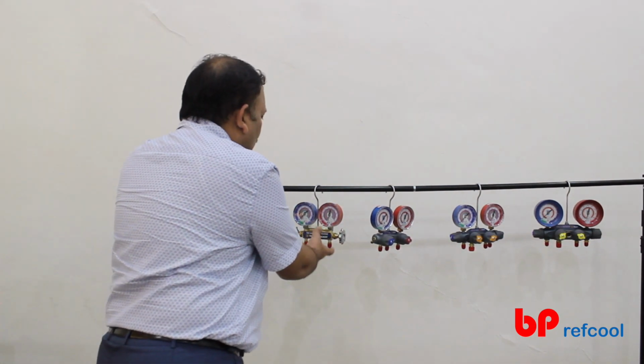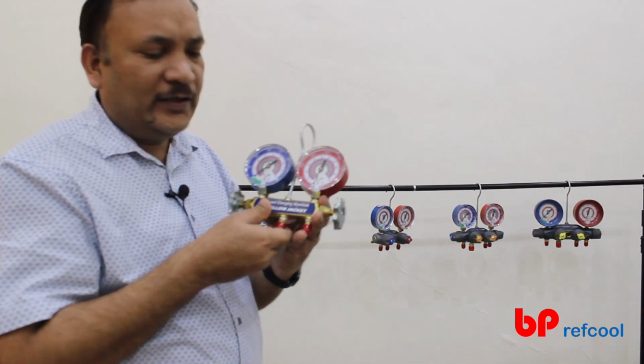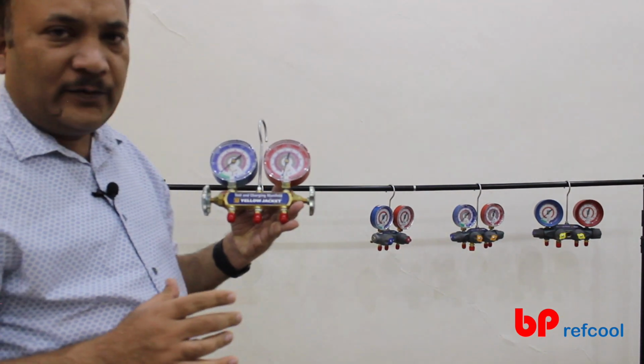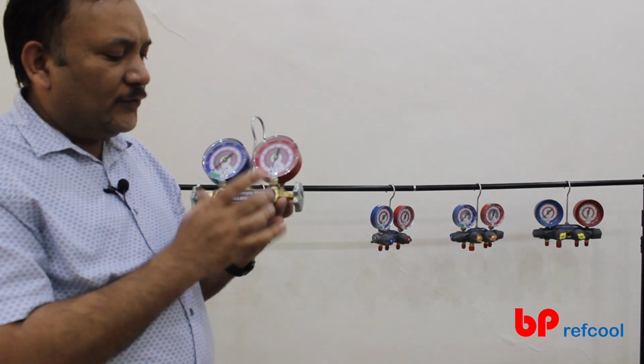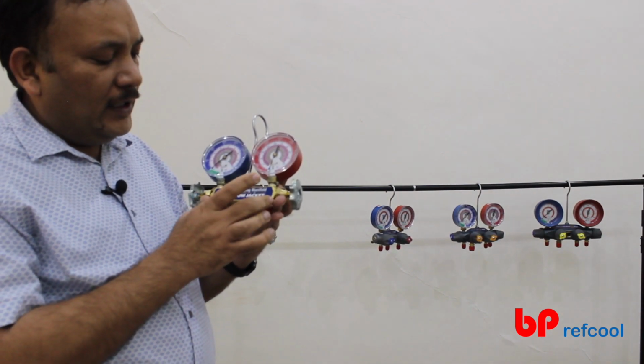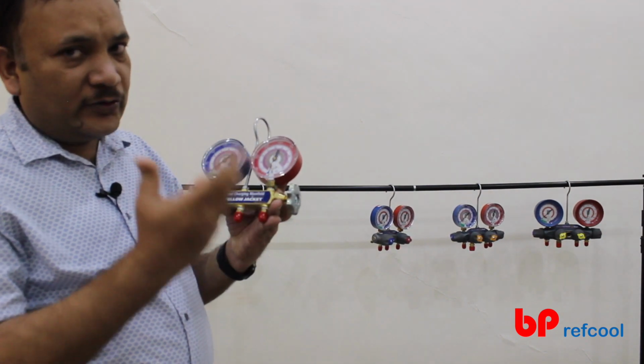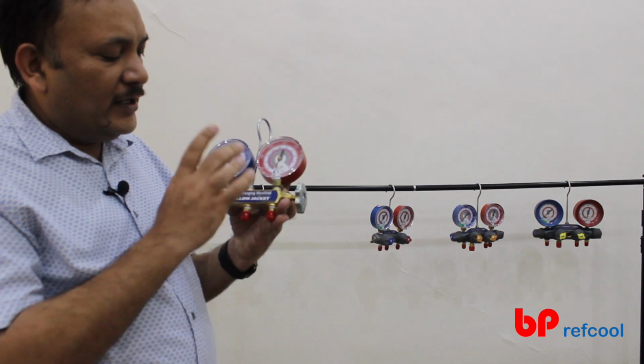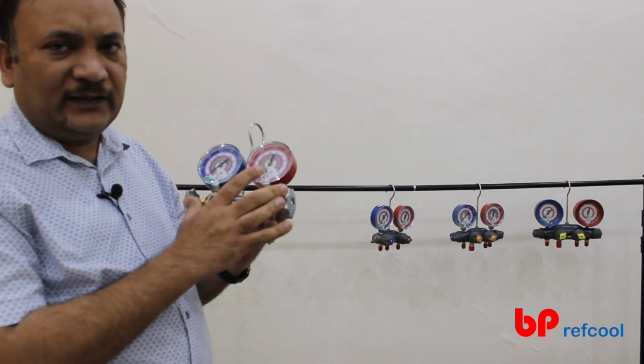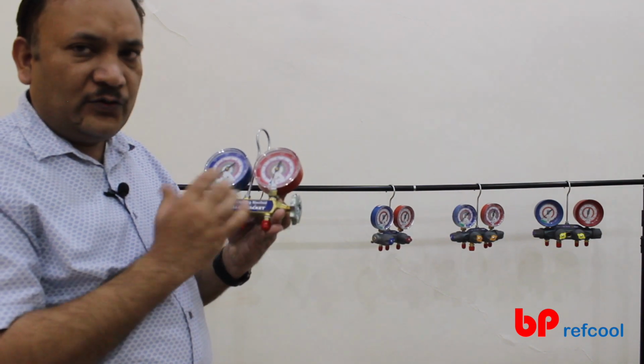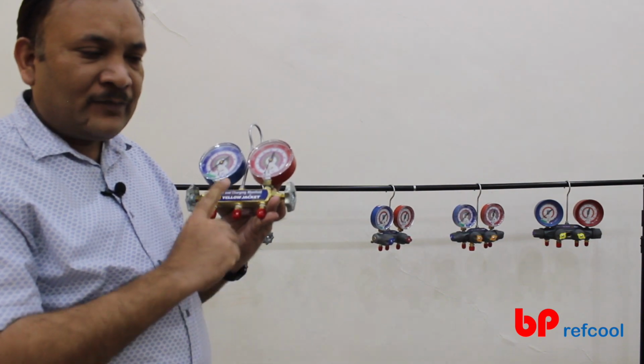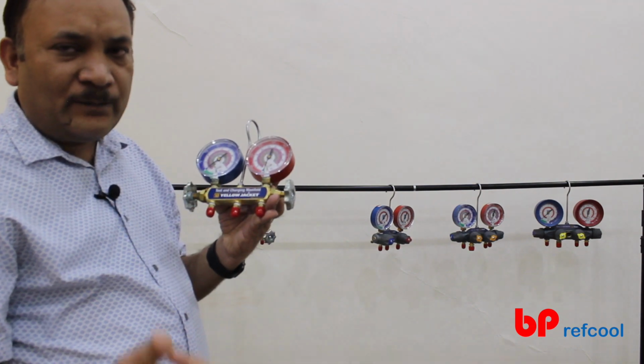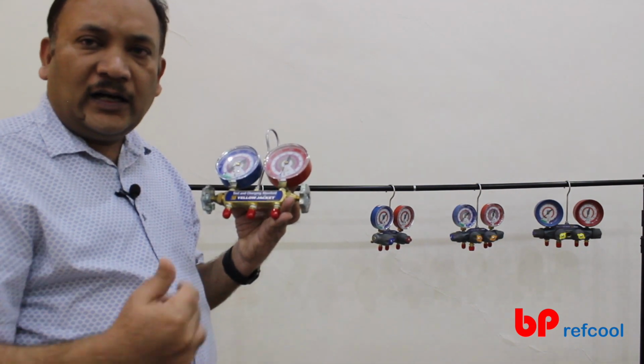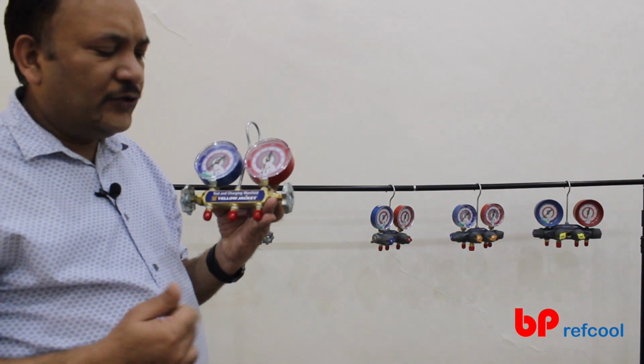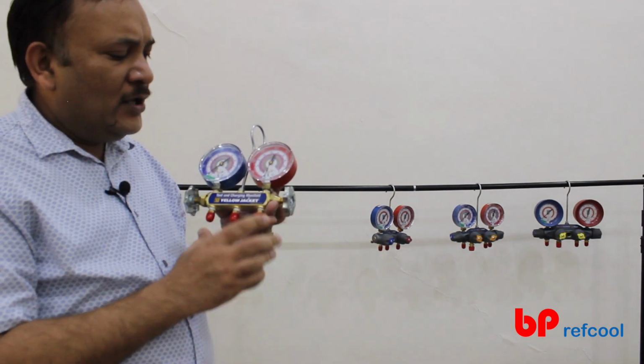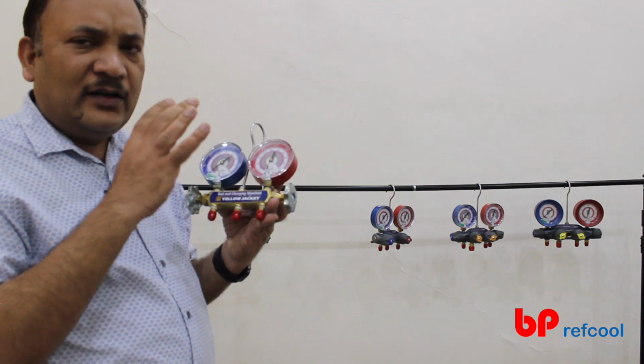So now we come to the second type, which is series 41 manifold gauge, which is solid brass, high pressure manifold gauge. We talked about the typical features of a manifold gauge. In this we already know that yes, this is a two-way manifold. You can manage both, but the center one is something which first you connect to the vacuum and then you connect it to the charging cylinder, so you can do the gas charging and all that stuff. So this is typically very common.